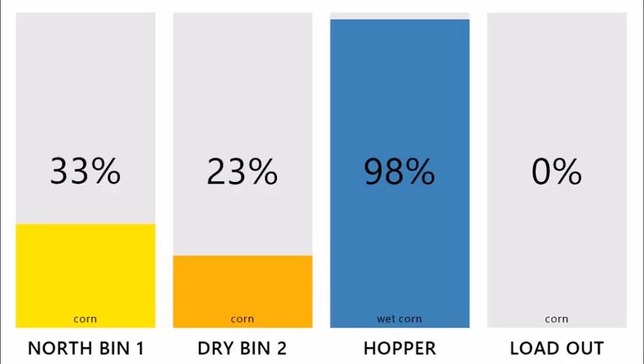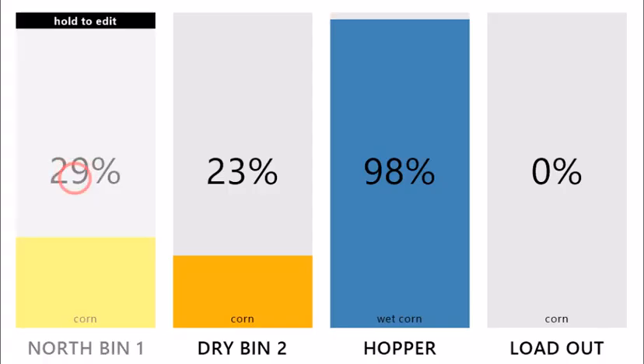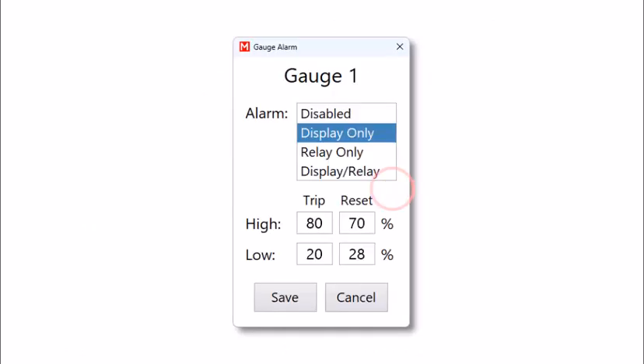Now that we've seen how the alarm levels work, let's take another look at our other alarm options. Relay and display/relay are our remaining options for alarms. We've covered what the display half of the last option is, but let's talk about the relay portion. There are 5 ports on your full view monitor. The first 4 ports are for sensors to be plugged into the system. The remaining port is labeled RLY. That one is the relay port.